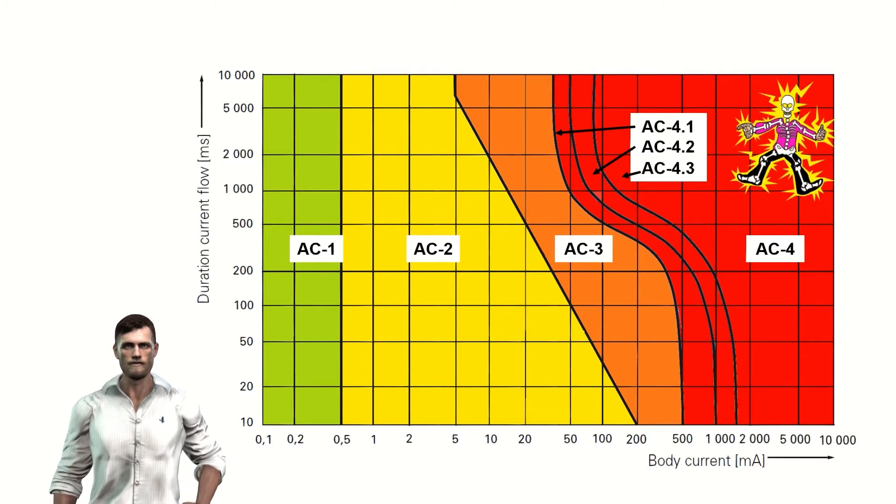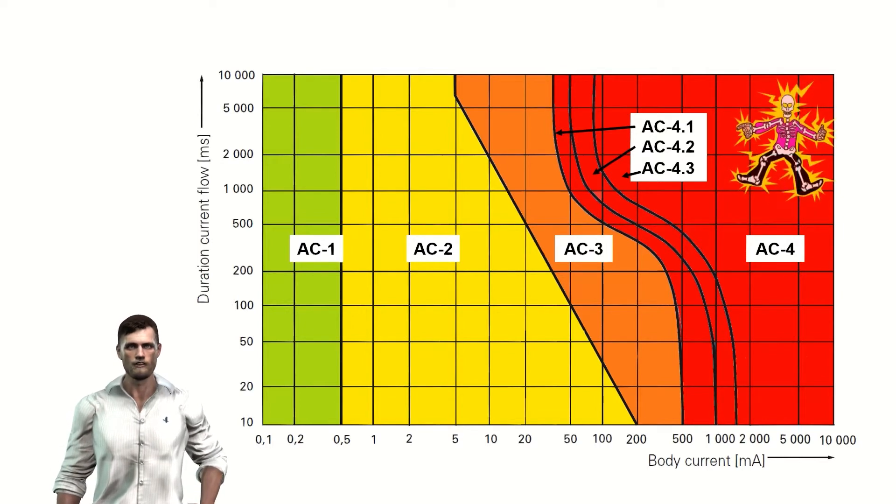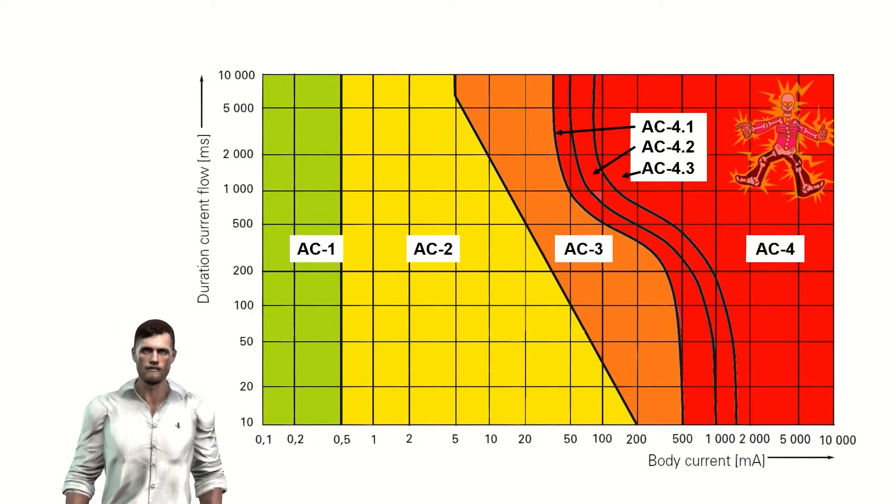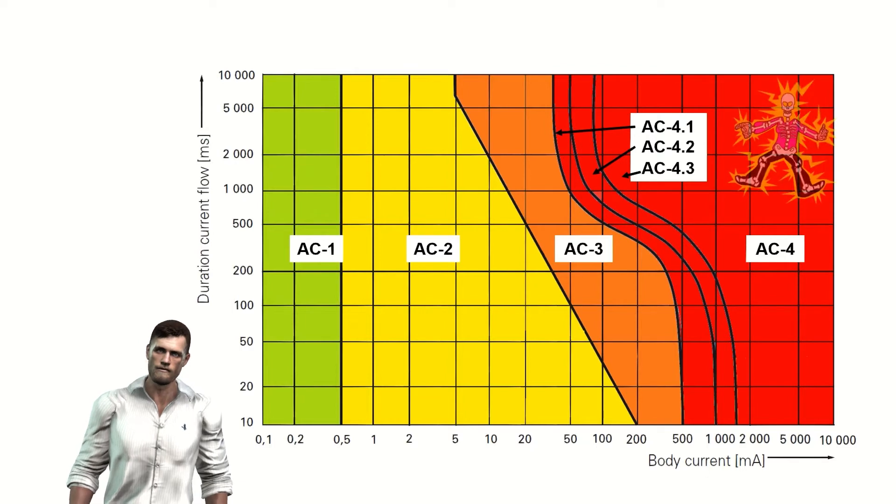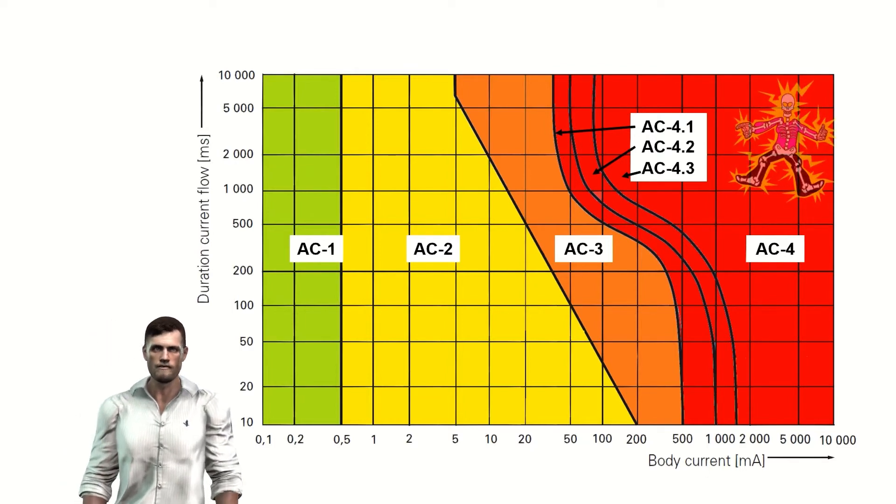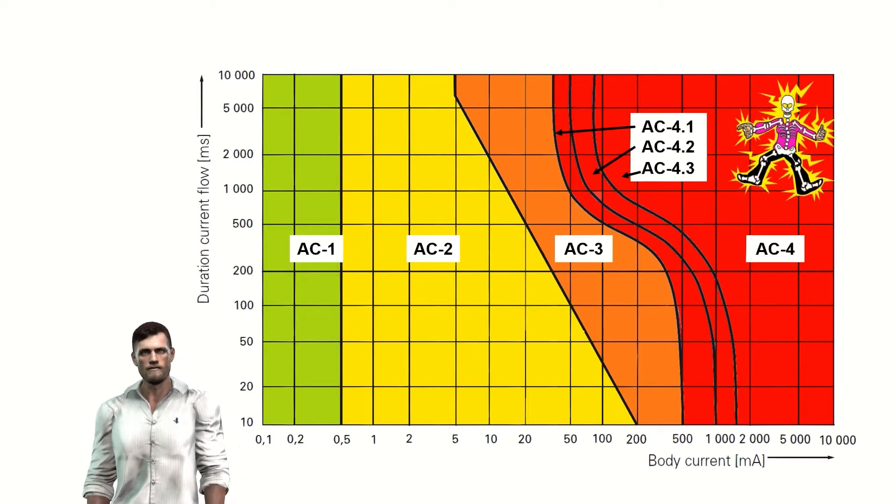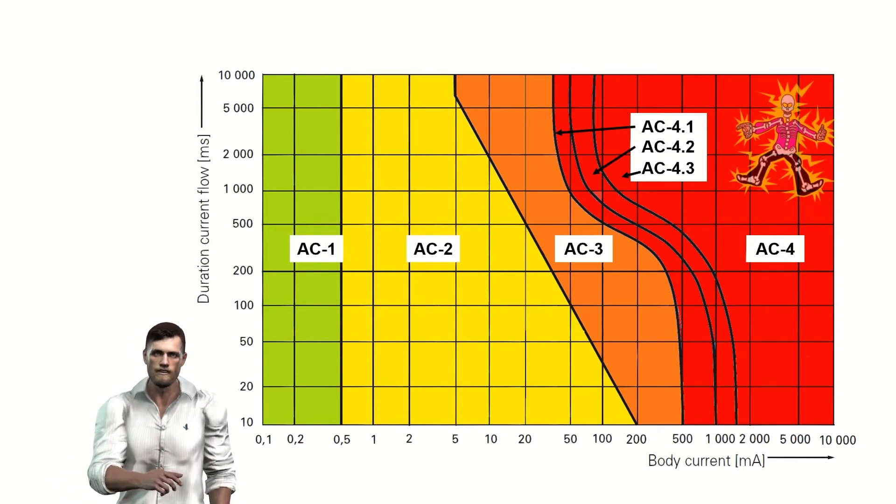In zone AC1, the effect of the current is practically imperceptible. In the AC2 zone, the passage of the current would already begin to be perceptible. In zone AC3, we would already have muscular contractions but the effects, in principle, would continue to be reversible in most cases.